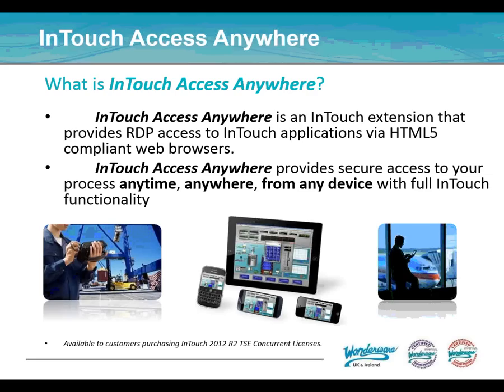So what exactly is InTouch Access Anywhere? We are talking about an HTML5-compliant RDP session, in effect. It works in the same way as terminal services. You install a lightweight piece of software on the terminal server and that manages the integration to the web browser. When you go to the website, it essentially opens an RDP session at the terminal services side and renders everything in an HTML5 view so that you can see it on screen and on your mobile devices. And it's actually included with InTouch 2012 R2 terminal services concurrent licensing — so there's nothing else to buy from a licensing perspective, providing you have that type of license.